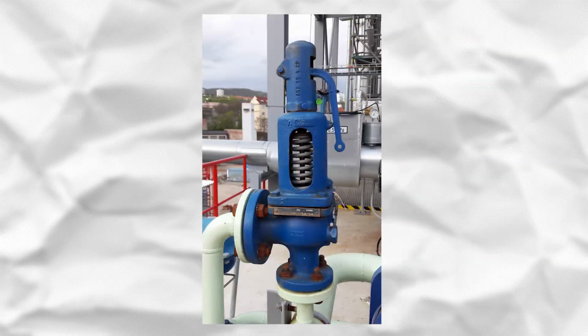Same as many other devices, PSV might be supplied with some accessories. You may select a lifting device, a lever, for a PSV. Sometimes we do need to check the opening performance of PSV deliberately to ensure that the valve has not got stuck or jammed. Finally, I would like to state that there are many points and tips about valve which you need to consider for designing, sizing, and supplying.